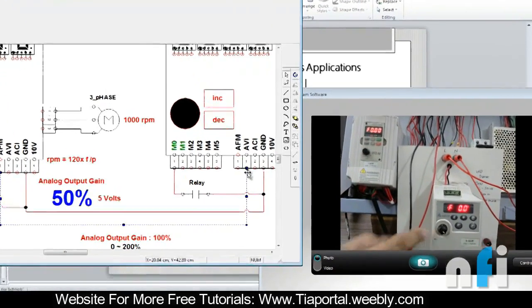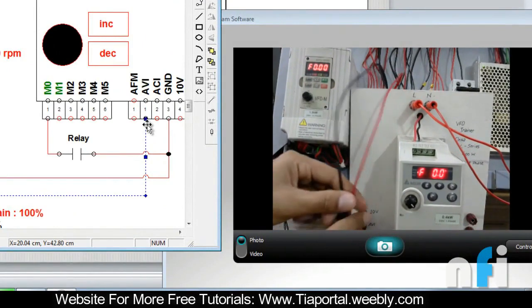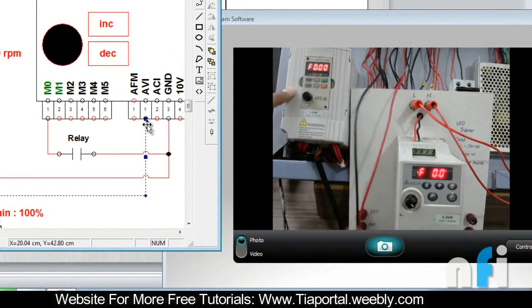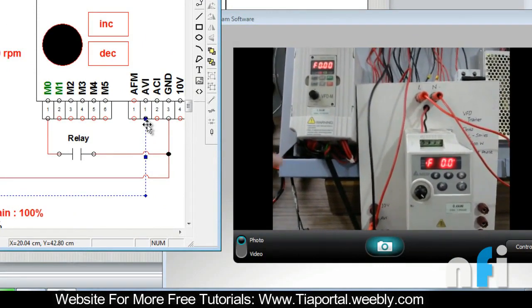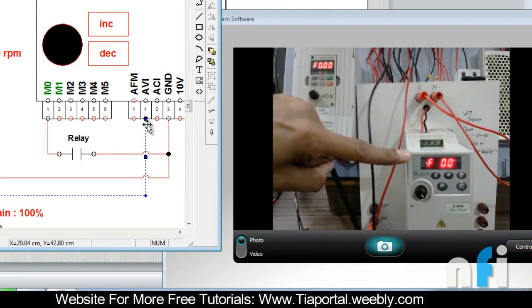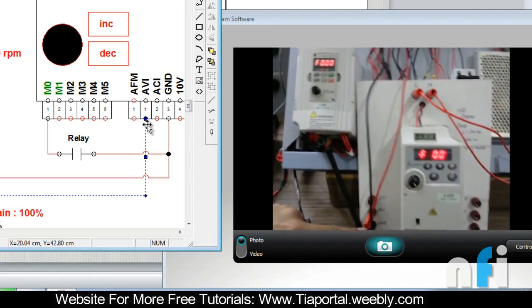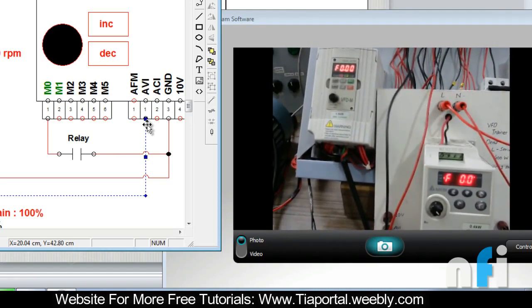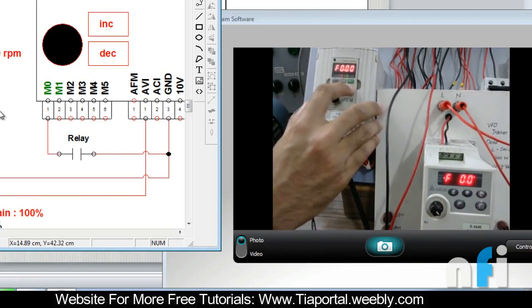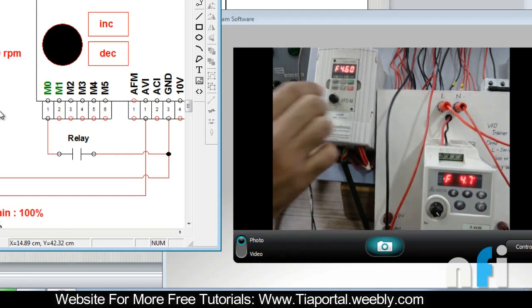The two wires are AFM and ground of the master drive, and these are connected to AVI and ground of the slave drive. You can see that's the AVI terminal and that's the ground. That's how we have done the wiring. This synchronizes the drives at a one-to-one ratio.